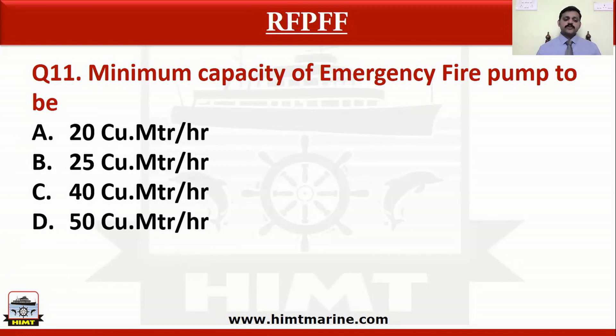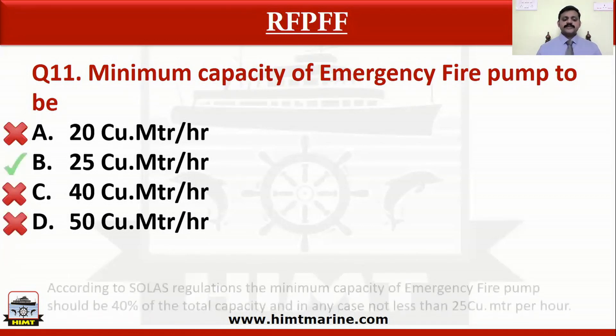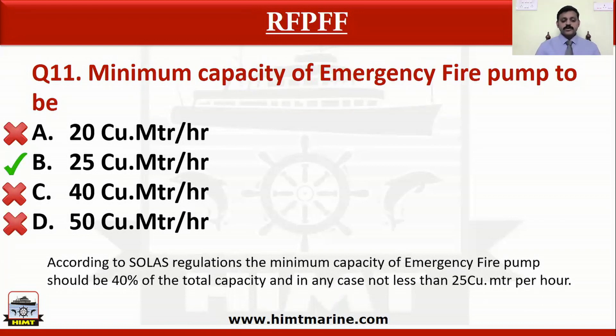Question number 11: Minimum capacity of emergency fire pump to be — option A 20 cubic metres per hour, option B 25 cubic metres per hour, option C 40 cubic metres per hour, option D 50 cubic metres per hour. The correct answer is 25 cubic metres per hour, because according to SOLAS regulations, the minimum capacity of the emergency fire pump should be 40% of the total capacity, and in any case not less than 25 cubic metres per hour.